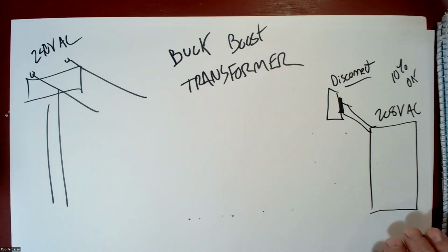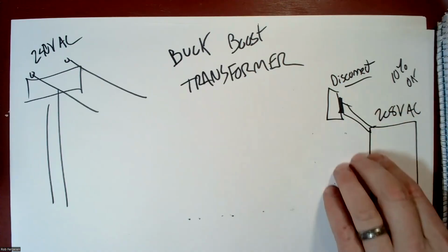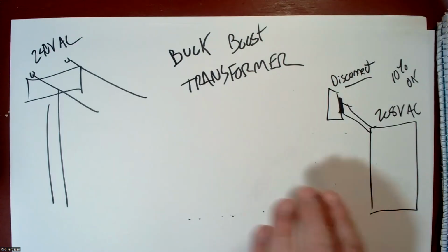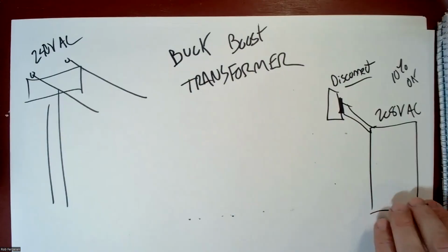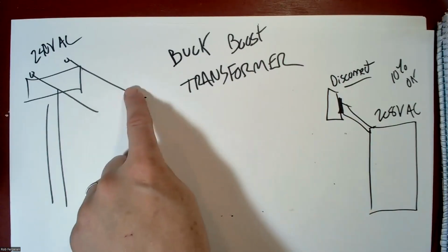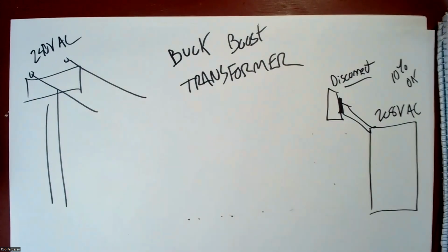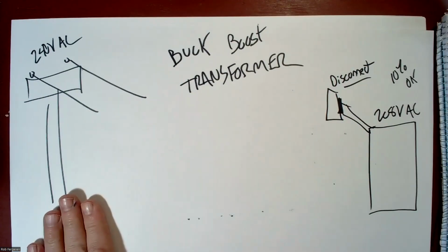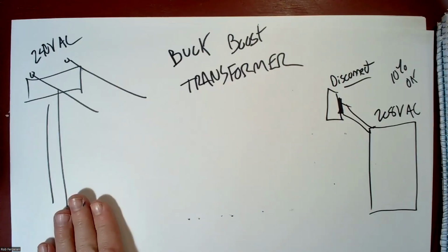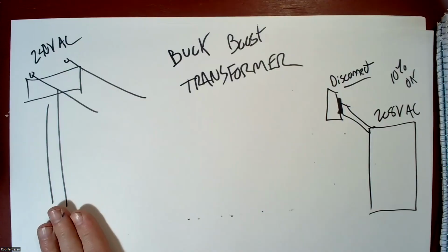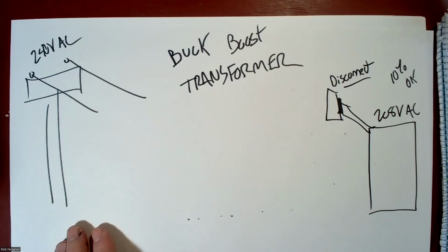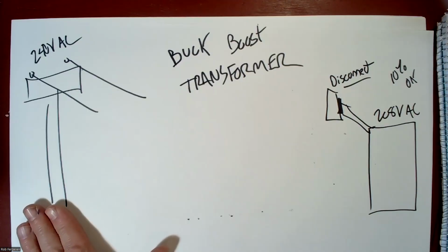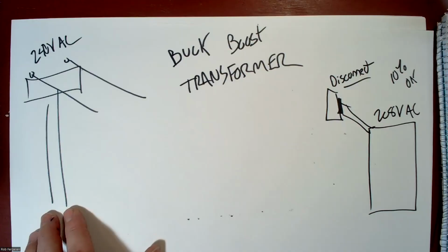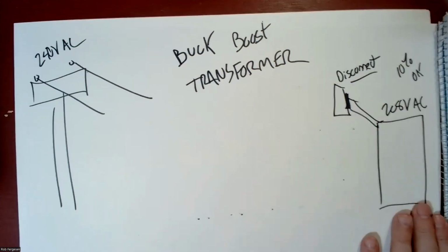By increasing or decreasing the voltage slightly, you're making that equipment more reliable to match exactly what you need in your building. Typically, also, many buildings have voltages that vary a little bit, especially in the summer when there's high demand. So what used to be 240 or 245 might drop to 230 or even lower. So something that would boost this 240 to say 250 means it's slightly high, but when it starts dropping in the summer, it doesn't drop so low that your 240 volt or your 230 volt equipment will be a problem. So a buck boost transformer handles all of those cases.